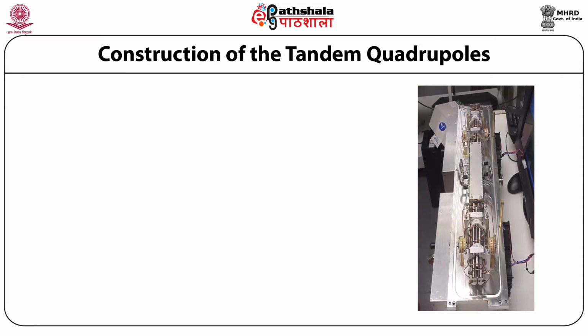What you see here is the inside view of this mass spectrometer and its construction. This arrow denotes the place where the ionized molecule enters the quadrupoles. Here is quadrupole 1, and there is a box afterwards that encloses quadrupole 2, the collision cell where the fragmentation happens.